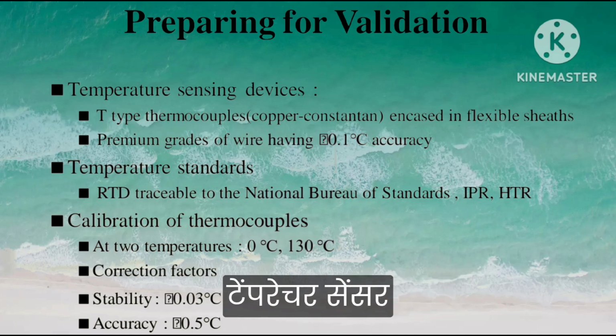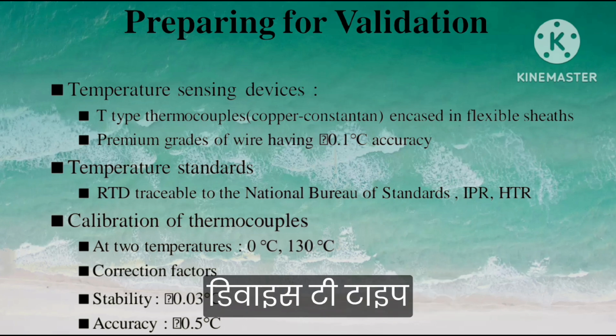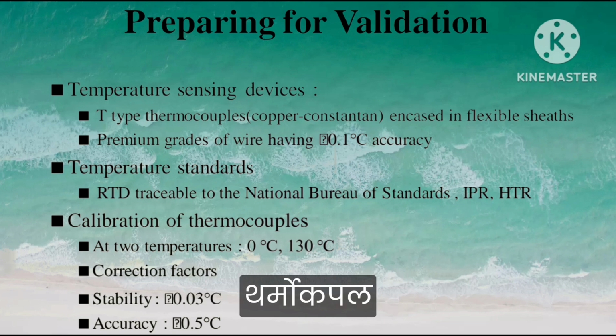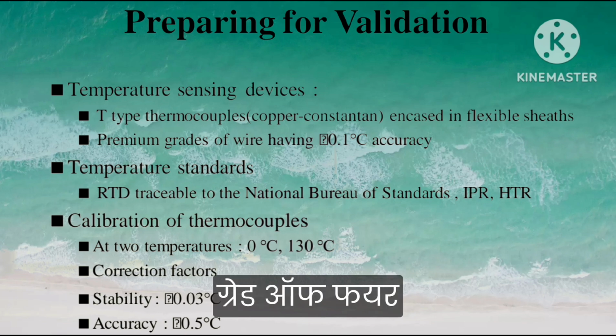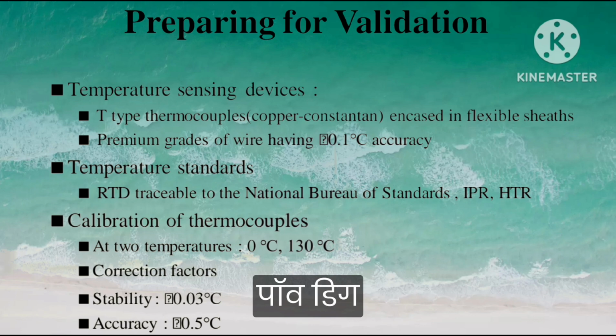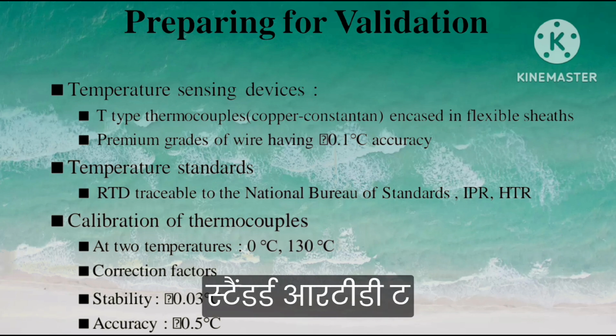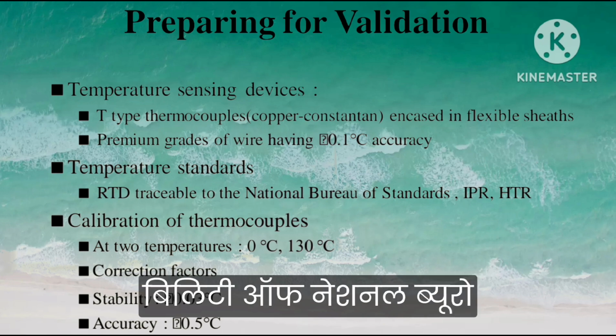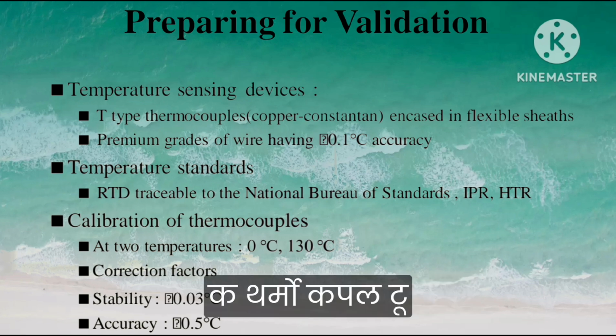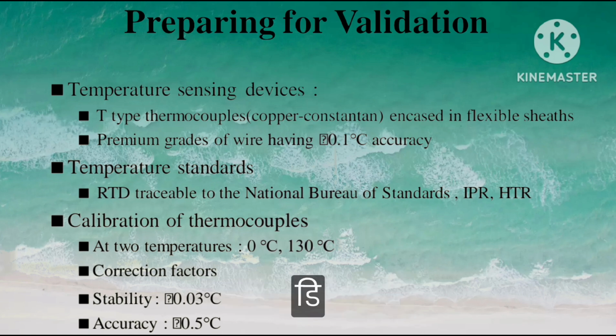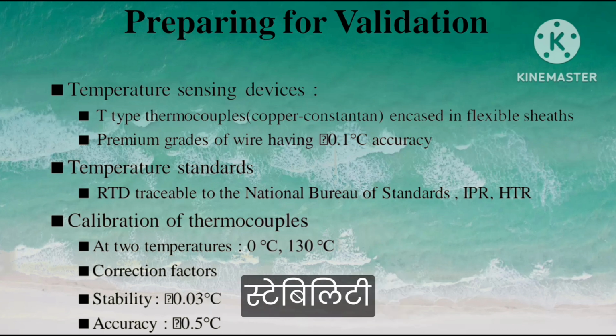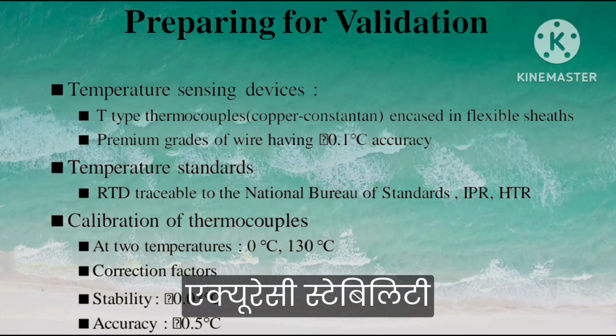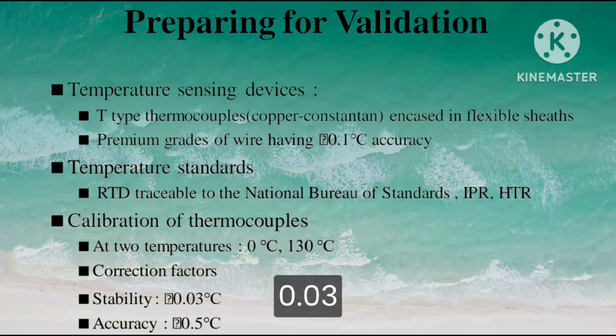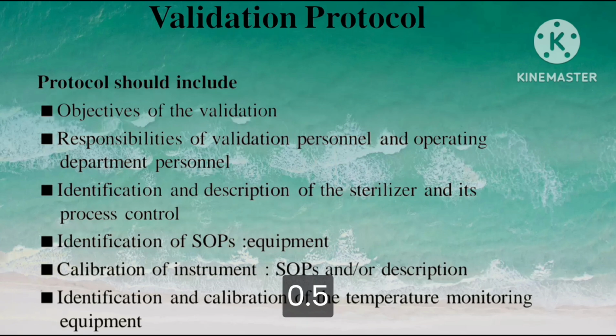Preparation for validation: temperature sensor device, T-type thermocouple, encased in flexible sheaths, premium grade wire having 0.1 degree centigrade accuracy, temperature standard, RTD traceable to the National Bureau of Standards, calibration of thermocouple at temperature 0 degree or 130 degree centigrade, correction factors, stability, accuracy. Stability is 0.03 degree centigrade and accuracy is 0.5 degree centigrade. Preparation for validation.